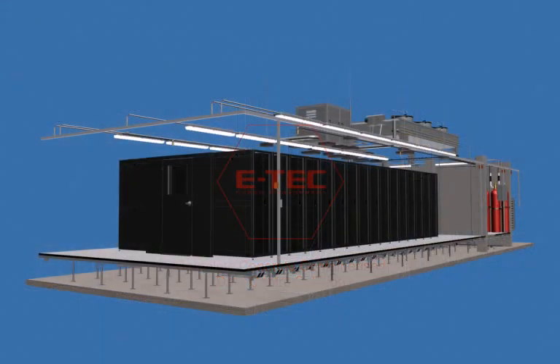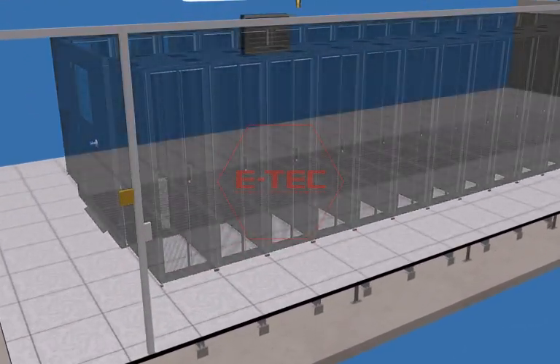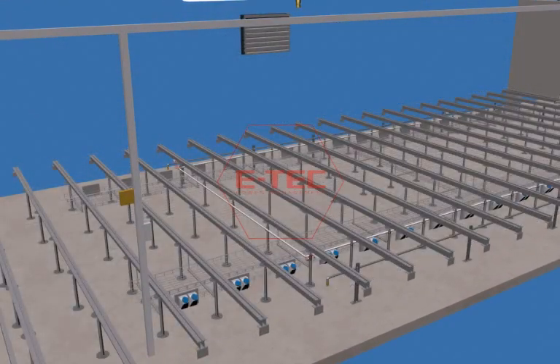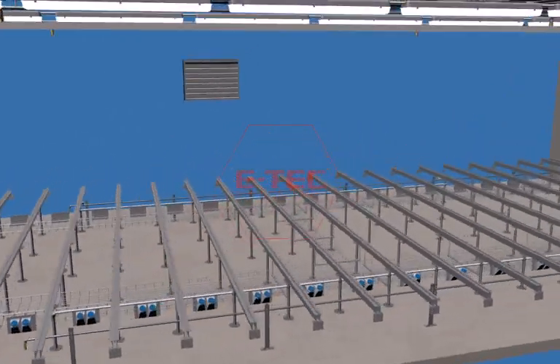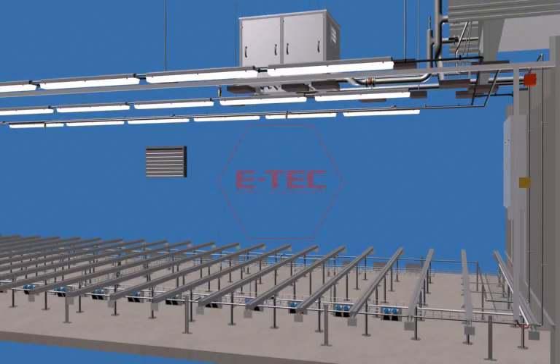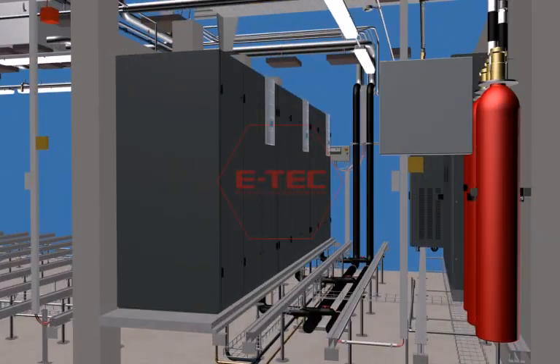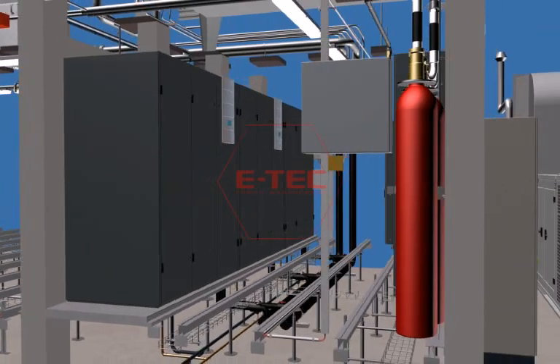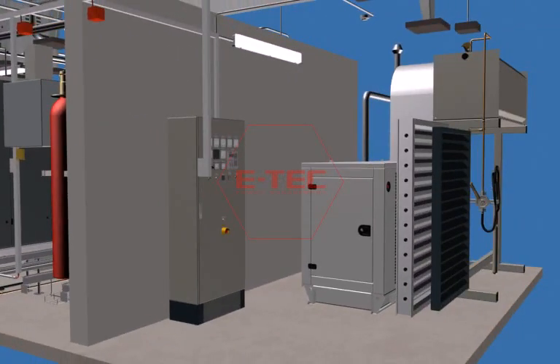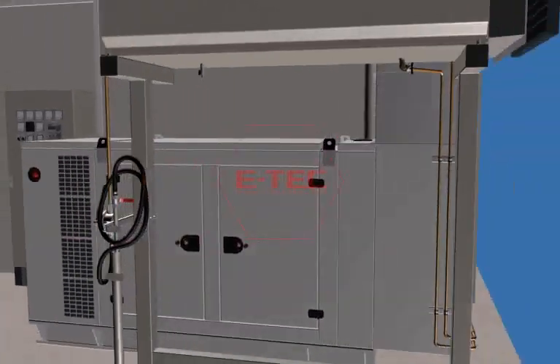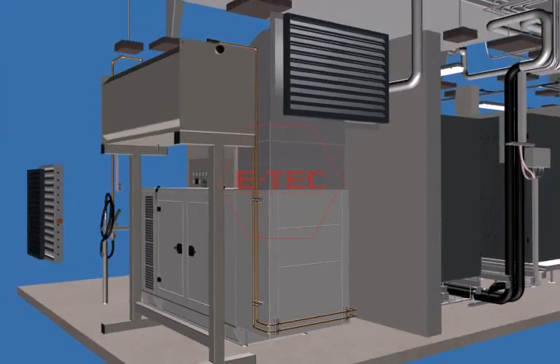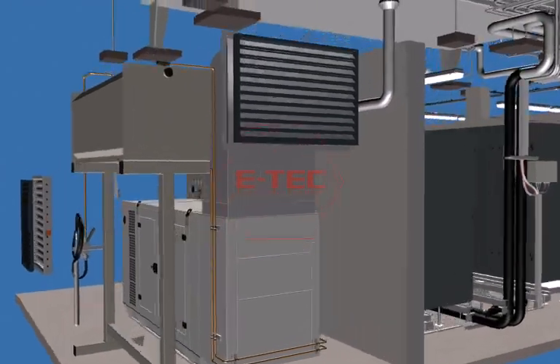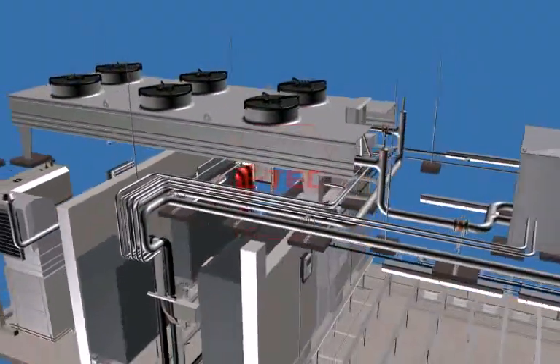The server room has a raised floor and rack cabinets assembled with cold aisle containment and with power supplied by A and B wall-mounted distribution panels. The adjoining room also has a raised floor and contains the switchgear, UPS, downflow units and fire suppression system. Lastly we have a dedicated generator room with appropriate level of sound attenuation. On the roof we have the chiller and pump house.